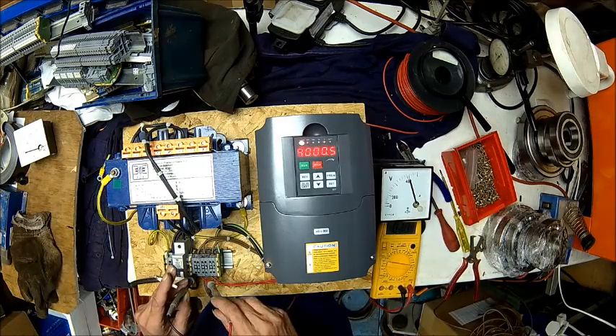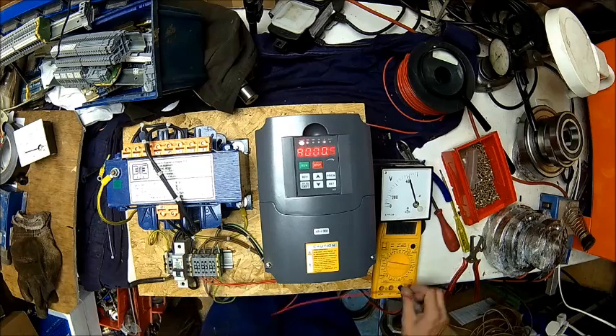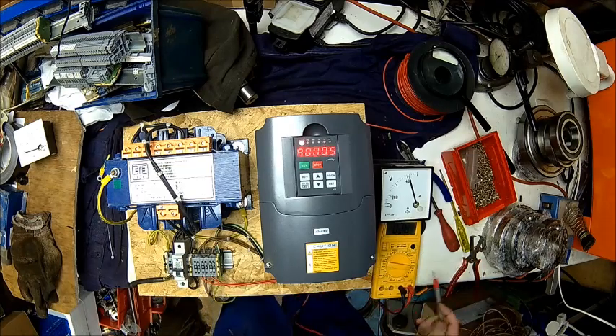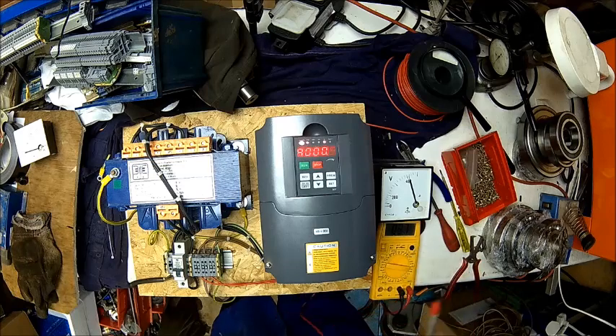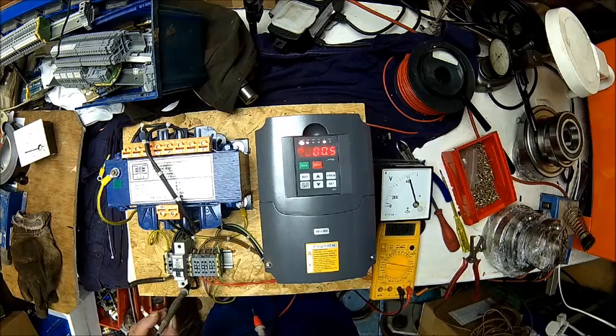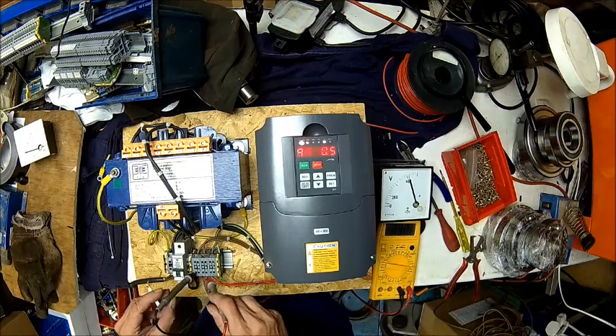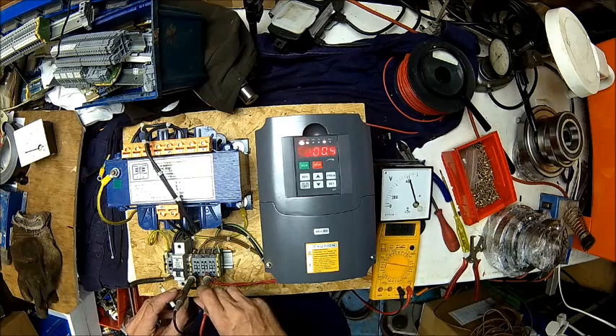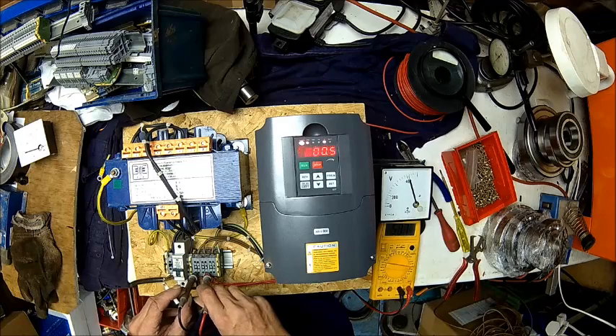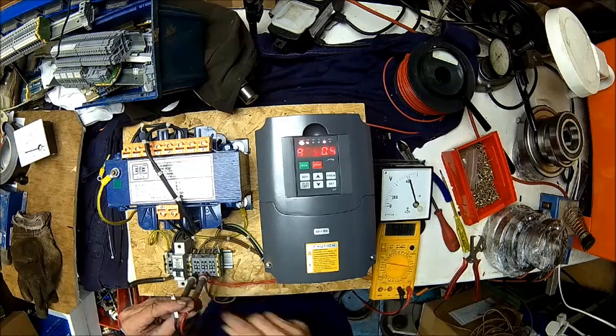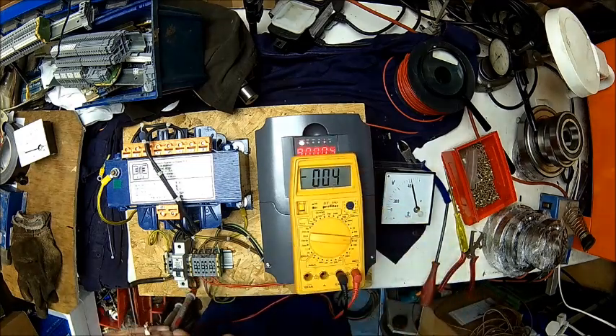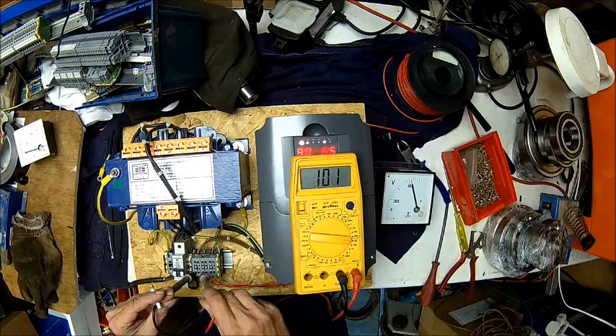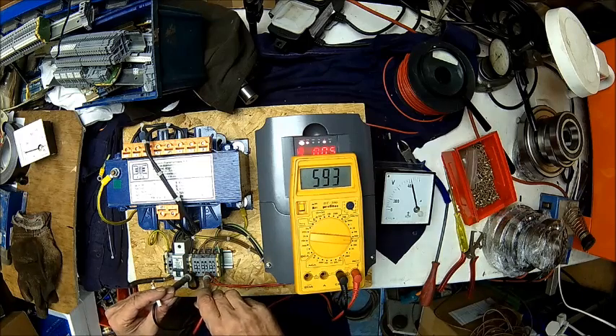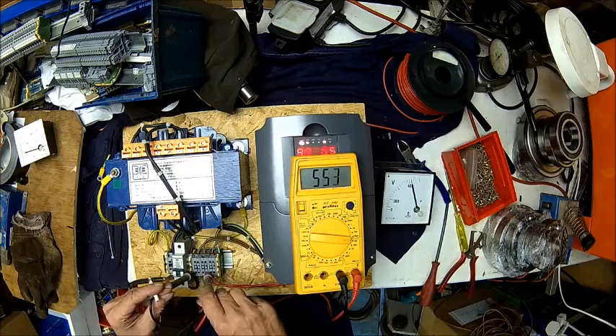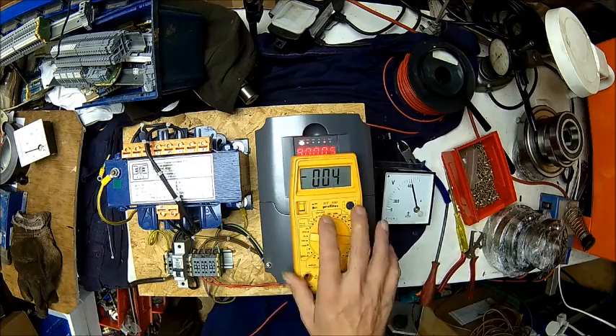I measure on the same terminals, and oops, our lovely meter is reading 570 volts, 580 volts. So put it on top of here. So it's reading 560, 580. That's our DC peak voltage, what we're measuring here.